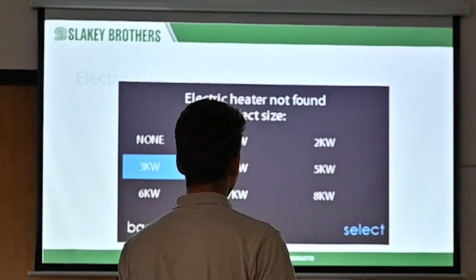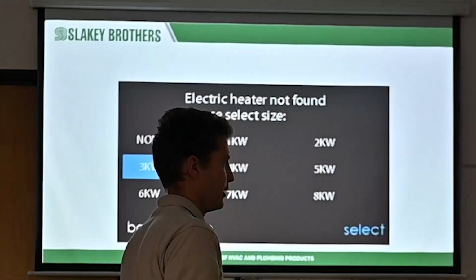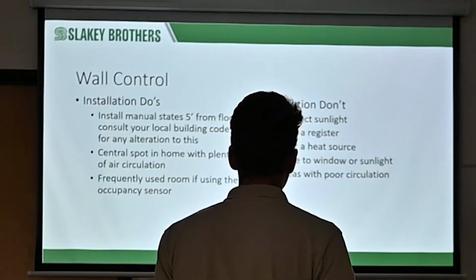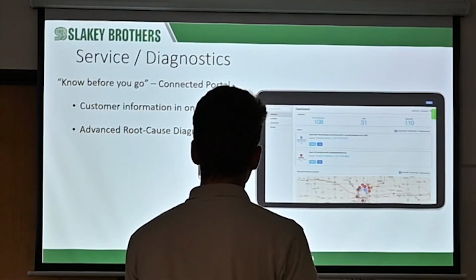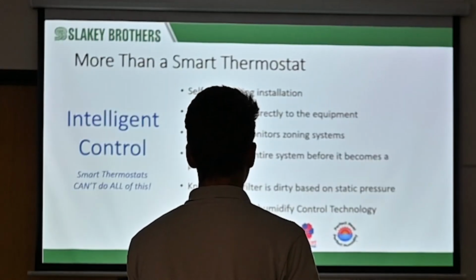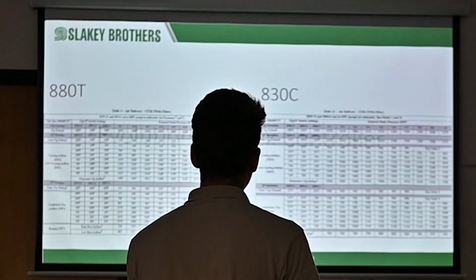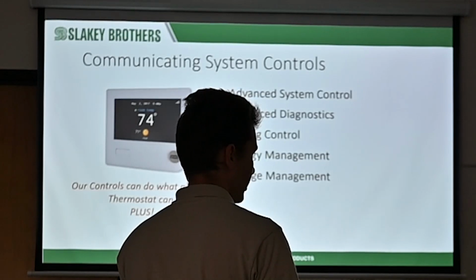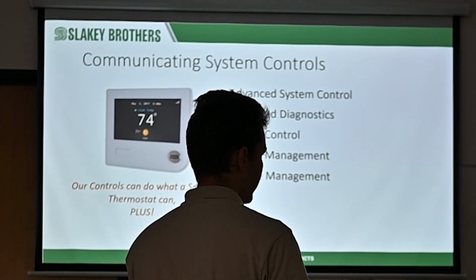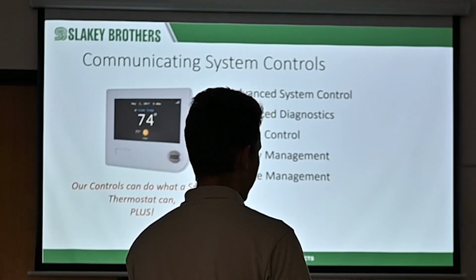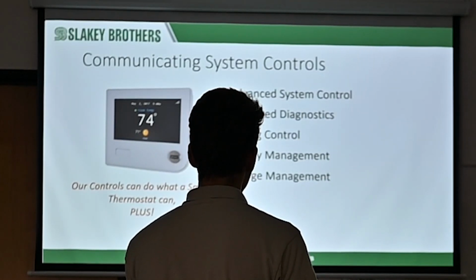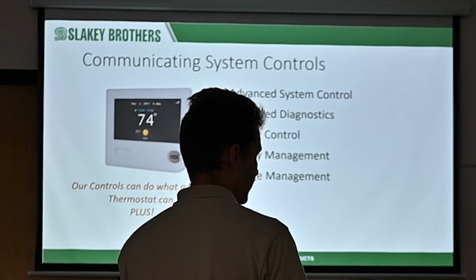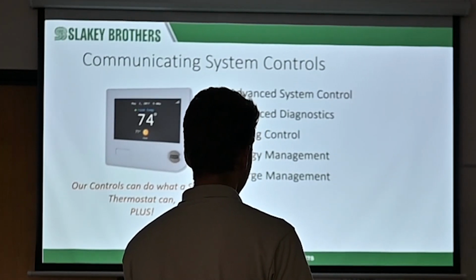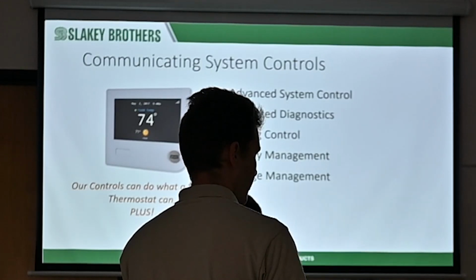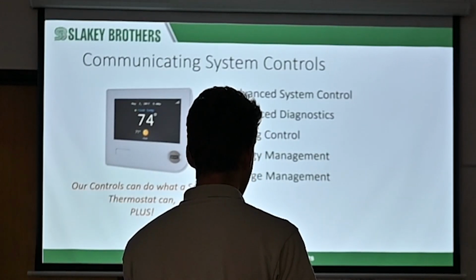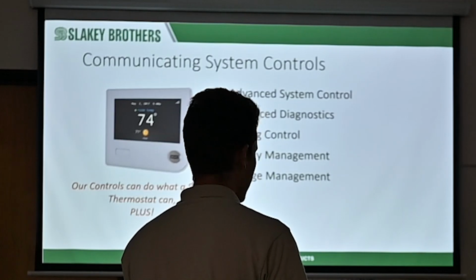I don't know, maybe it's better to ask when the other guys are here. When we do airflow setup, there is a whole section later on for airflow setup. Like I said, this is why I wanted to take a break, because the Connex, we used to do a class that was 3-4 hours just on the Connex, because it could do so much. We're going to go over the important stuff, which is the setup. Installing and configuring it is easy. The rest is the setup: how to make sure you have the right airflow for your furnace and for the fan coil, and any set points for the condenser.